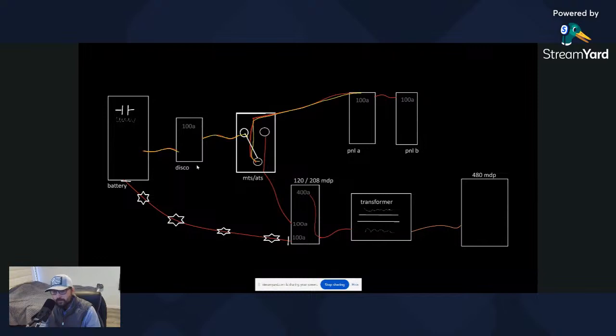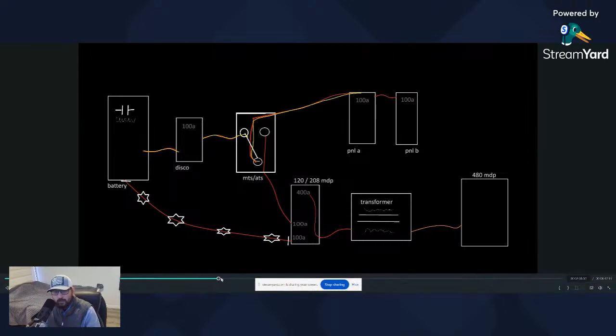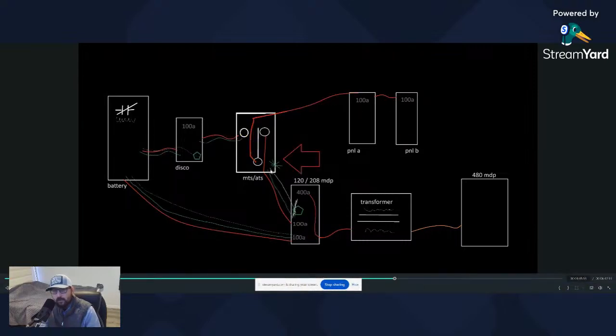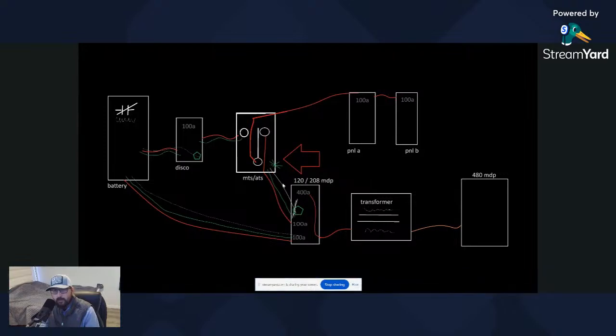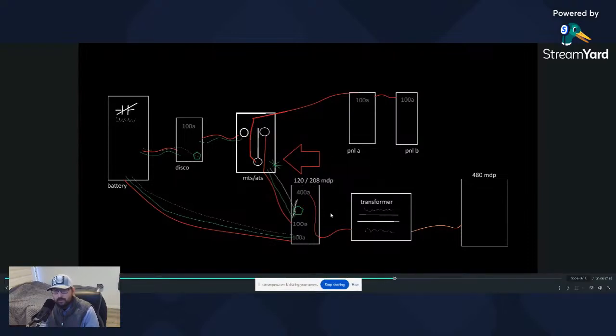We added this disconnect. The plans didn't call for this. We got to talk to the engineer and get them to add a disconnect, because one, we needed it, but we also need a space to bond. The last thing we want to do is bond inside this ATS, because if we bond in this ATS, we're going to create a parallel path, and we're going to get current on our ground and on our neutral. 1.732 would be the three-phase calculation for that, but just pretty much figure in half. Half of the current goes on the ground, half of the current goes on the neutral. So you don't want any current on your ground wire, obviously. So you bond here, and then pretty much everyone's happy. Not so common though. It's not always obvious where you want to bond. It really depends on where your neutrals come together on the ground points.